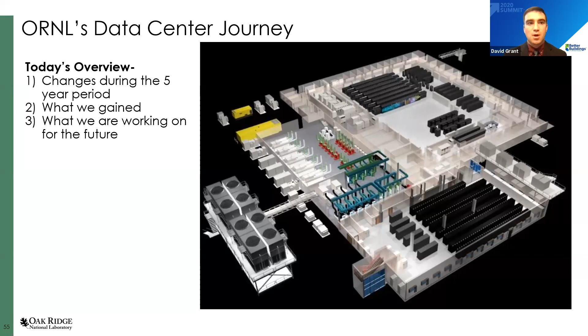So before the data center that we'll talk about today was built, we were largely chilled water based with water-cooled centrifugal chillers. And we had roughly 8 to 10 megawatts of data center load coming back to that chilled water plant that you can see towards the middle of the screen with the red pumps. So back when we first started, we had that setting and we had a design for our 2018 new high performance system, which would be called Summit, which was going to take the place of Titan, which was actually retired in the summer of 2019. So today we'll talk about what we gained, a little bit about the journey and the design, and what we're looking towards in the future. Next slide, please.